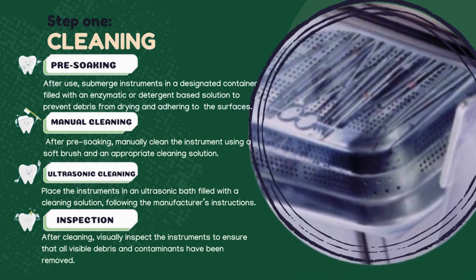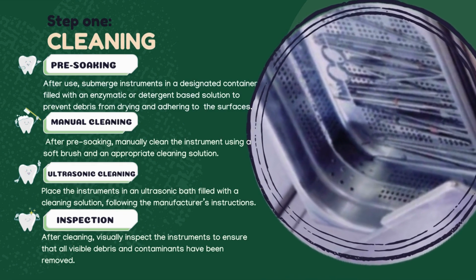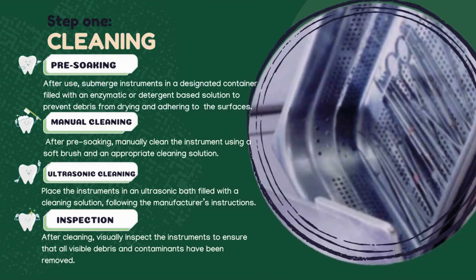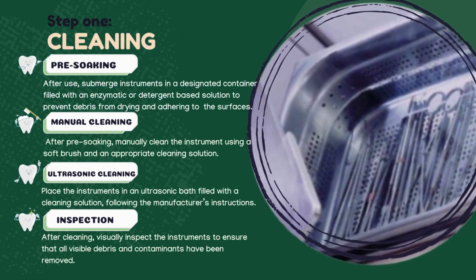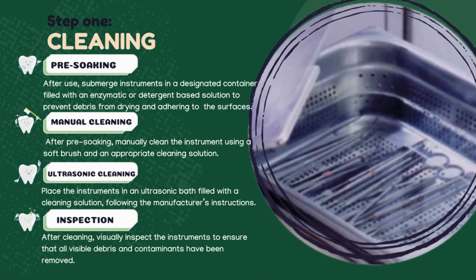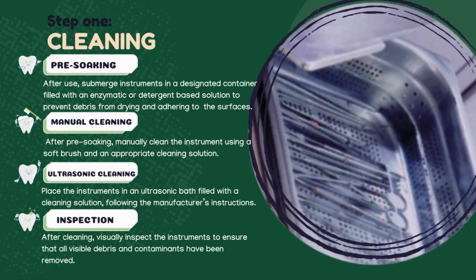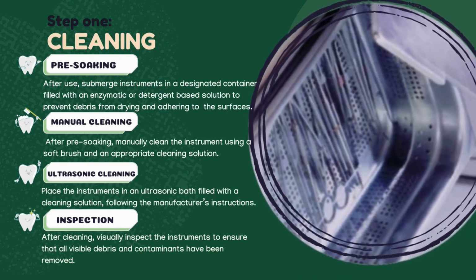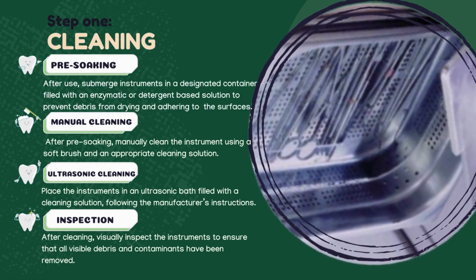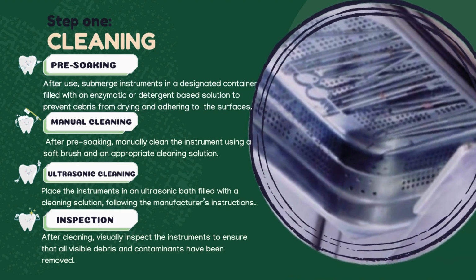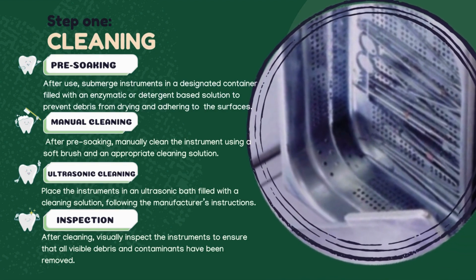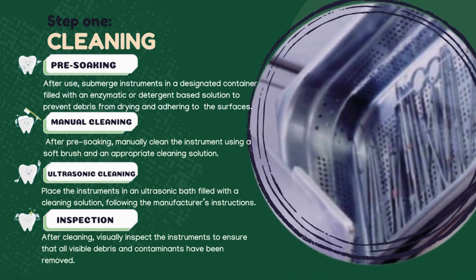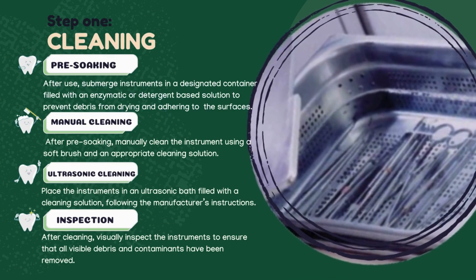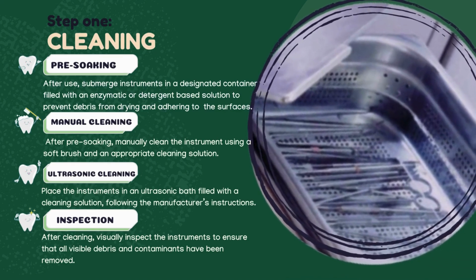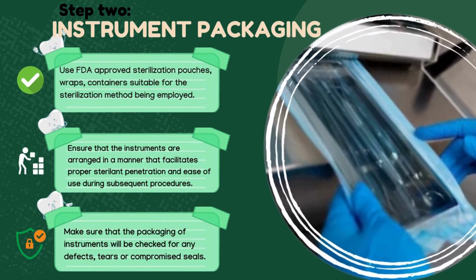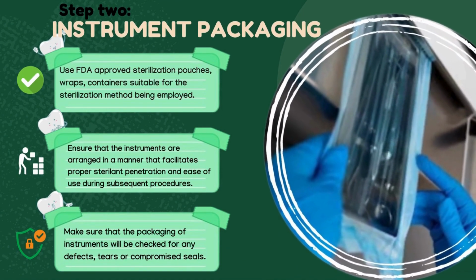First thing is, number 1, pre-soaking. After use, submerge instruments in a designated container filled with an enzymatic or detergent-based solution to prevent debris from drying and adhering to the surfaces. Manual cleaning. After pre-soaking, manually clean the instrument using a soft brush and appropriate cleaning solution. Ultrasonic cleaning. Place the instruments in an ultrasonic bath filled with a cleaning solution, following the manufacturer's instructions. And last is inspection. After cleaning, visually inspect the instruments to ensure that all visible debris and contaminants have been removed.